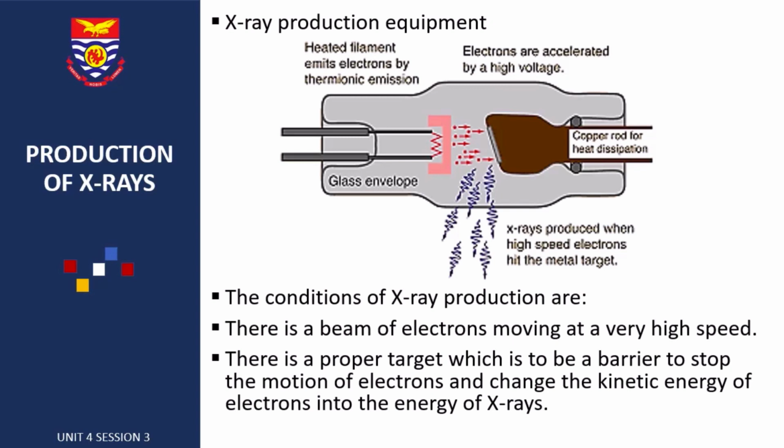There are three basic components in this X-ray equipment. One is the X-ray tube, one is a low voltage power supply, that's our electrical source, and one is a high voltage supply. The vacuum tube uses a high voltage to accelerate the electrons released by the hot cathode. The high voltage electrons collide with the metal, that's the anode, and that's creating the X-rays.